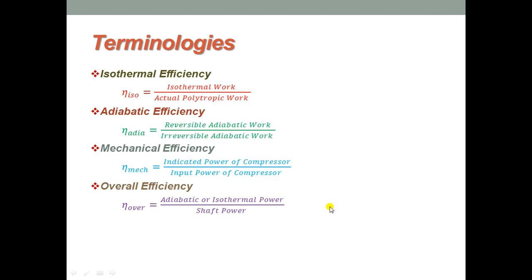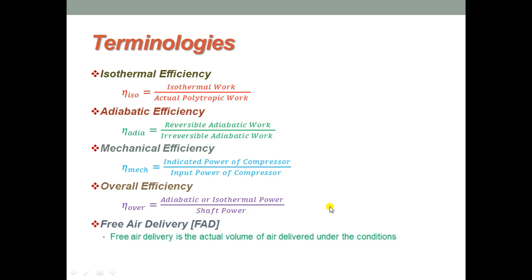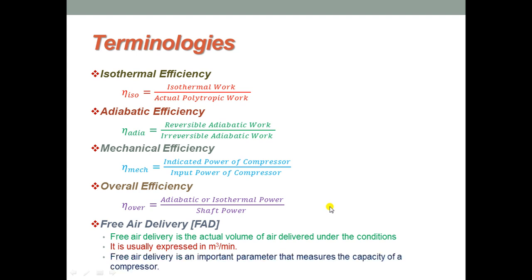One important terminology is free air delivery, or FAD. Free air delivery is the actual volume of air delivered under the conditions of temperature and pressure existing at the compressor intake. It is usually expressed in cubic metres per minute. FAD is an important parameter that measures the capacity of a compressor in terms of air flow it can handle, and is normally measured at standard sea-level atmospheric conditions.